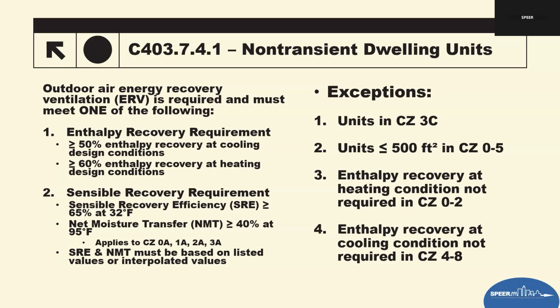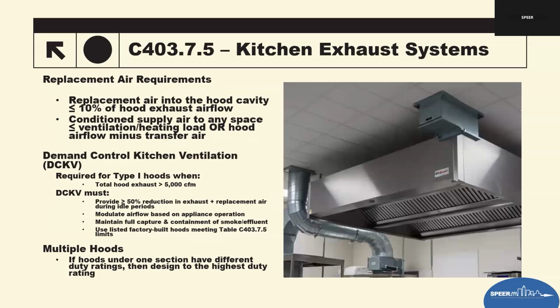So check the climate zone to determine which exceptions may apply. And then field inspection tips: verify the ERV installation matches submitted ratings. And then check airflow balancing, so supply and exhaust ratios, as well as confirm condensate drainage for the ERV. That's very important, especially in humid climates. And then inspect the controls for frost prevention and bypass functions. Probably not so much in Texas, but check those as well. Commercial kitchens, those have changed up just a little bit with the exhausts that are in that.